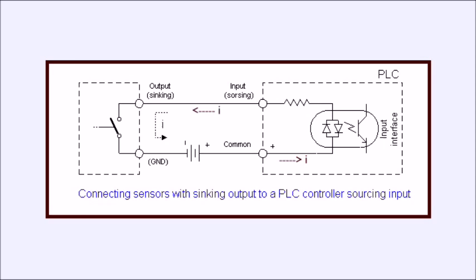This is an illustration taken directly from a PLC service manual and illustrates what we have to call source and sink. This determines how the sensors are connected in these and also the outputs too for that matter. We are looking at it from the viewpoint of a current loop. If we have a current flow through the optocoupler back through the switch to the return on your power source, in this case this is the sinking output because your current loop has to be completed on the negative side of the source. Once it's switched on the LED does its thing turning on the photo transistor and telling the microcontroller hey the switch is closed. This is the sink configuration.